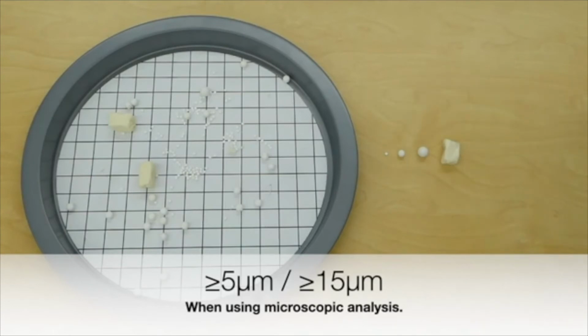Now, ultimately, if I am looking at particles greater than 5 micron, then these little ones get excluded. It doesn't matter how many I have on here. It doesn't matter how many I have in my system. They don't get counted. They don't get reported, because they don't meet the grade. Ultimately, that should be okay because, generally, particles that are 3 micron, 4 micron and smaller are not very damaging to the system. Okay.